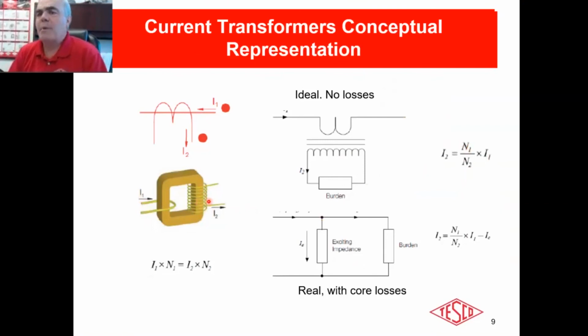I know that we've talked about it before, but I'll say it again. The reason that we use everything to 5, 200 to 5, 400 to 5, 1,000 to 5, 2,000 to 5, 6,000 to 5, 8,000 to 5, the reason we do everything to 5 is that the very first commercial industrial meter that was developed back in the late 1890s, I believe it was 1898, by Westinghouse, it was most accurate at 5 amps. So everybody tried to set their service so that they were getting 400 amps to 5, 200 amps to 5, 50 amps to 5, so that that meter would provide the greatest possible accuracy.